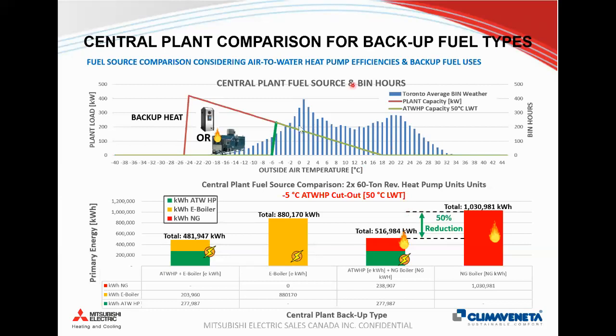Similarly, with the -5 example, we're going to use the heat pump down to -5 only, and then use a little bit more gas, because we do have a few more hours between -5 and -10. Our gas case is still fixed the same as in the last example, and with our air-to-water heat pump we're just using a little bit more natural gas. So instead of 400,000, we're using about 516,000 kilowatt hours, but that's still a significant reduction on a pure kilowatt hour basis, which is required as part of the design process for energy use intensity designs for buildings. So there are some significant kilowatt hour savings that can be realized, and the heat pumps can be leveraged as part of the design.